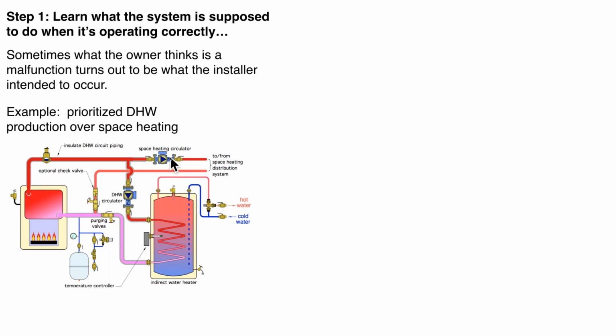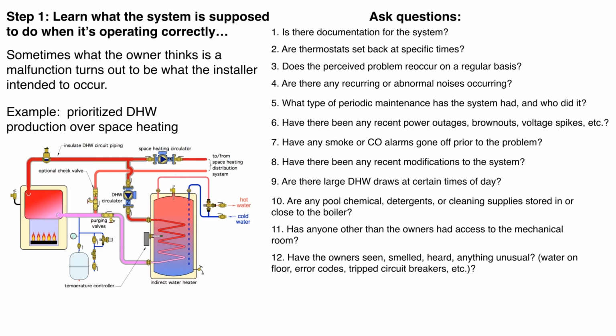And during that time, perhaps one of the spaces in the building cools down, and the owner assumes, oh, there's something wrong, that space is cooling down. And really, no, there's nothing wrong, because that's the way the system was set up. Now, if that's unacceptable, it's easy to make that domestic hot water circulator have the same priority as the other circulators, but we don't necessarily want to conclude that something is wrong simply because that's the current configuration of the system. So this is where you get to ask lots of questions to the owner.